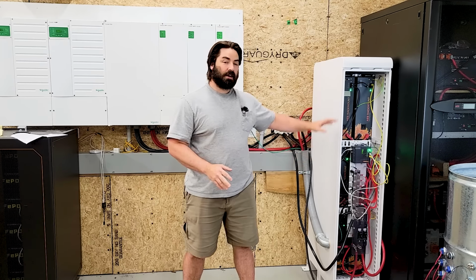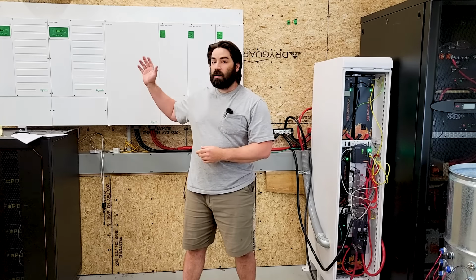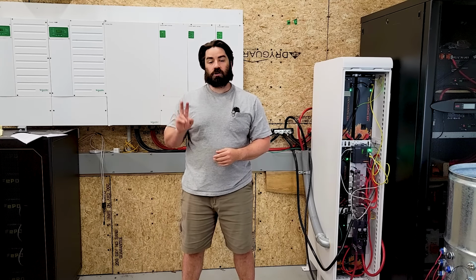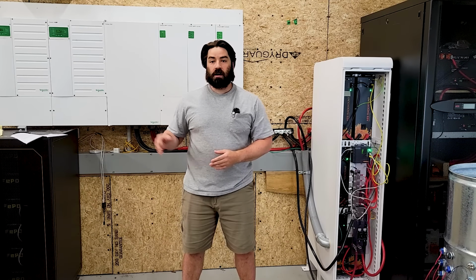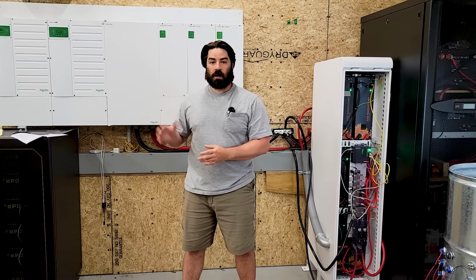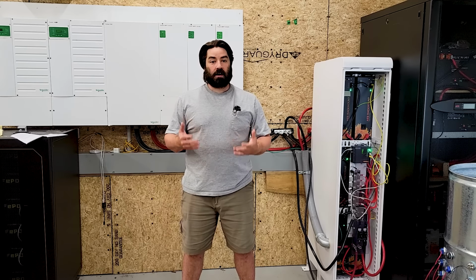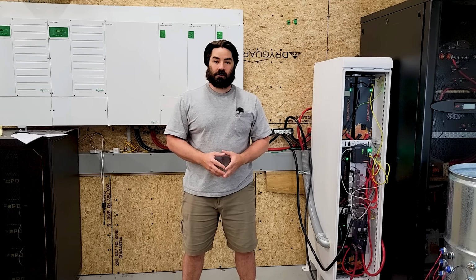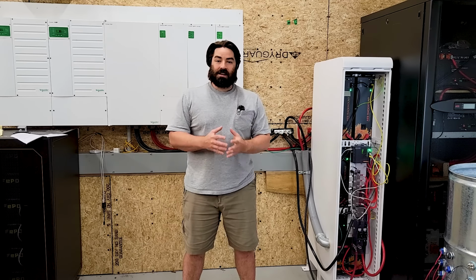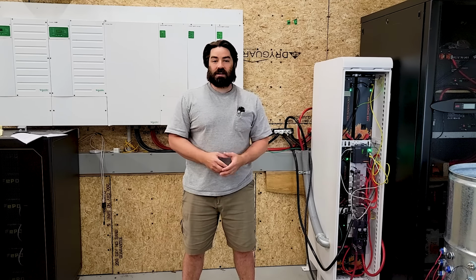Now I've got a couple of things hooked up here. I've got my inverter setup—these are 2 Schneider XW Pro inverters. Each one is capable of 6.8 kilowatts continuous and can surge a lot more. Now with these batteries, they can handle a huge surge, which is great because these inverters have a transformer in them that can also handle very large surges, meaning that if you have things like air compressors and air conditioners, you don't have to put soft starts on them.